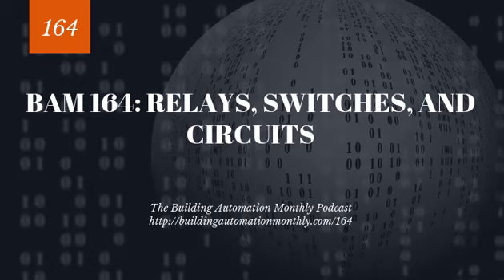So there's a variety of nuances you need to be aware of that we're probably not going to cover in this episode. But the reality is that is one of the most common types of status relays. As I mentioned, we don't want to put the relay inside the controller because we want to handle our amperage, our VA draw. We don't want to blow up controllers, and we want to have the ability to understand if our relays are on or off, and that's a quick glance, and it's also easier to troubleshoot with a multimeter.